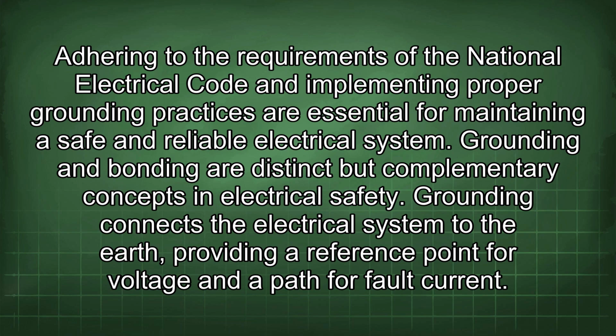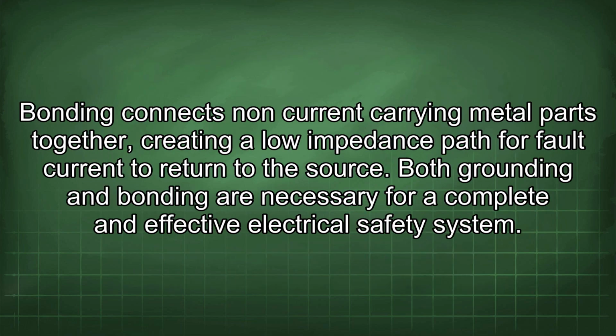and reliable electrical system. Grounding and bonding are distinct but complementary concepts in electrical safety. Grounding connects the electrical system to the earth, providing a reference point for voltage and a path for fault current. Bonding connects non-current carrying metal parts together, creating a low impedance path for fault current to return to the source. Both grounding and bonding are necessary for a complete and effective electrical safety system.